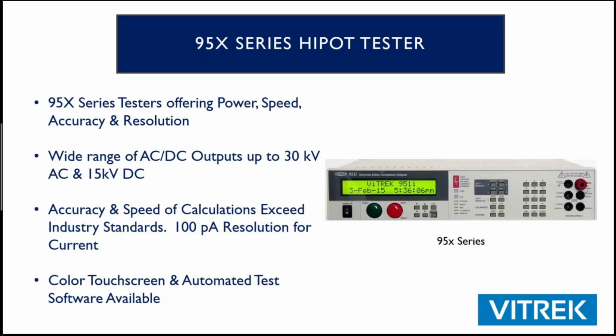So our other product family is the 95X. This product is more powerful, more accurate, and has a wider output voltage range. We can go to 15 kV DC, 30 kV AC. It's the most accurate tester, or as far as a HIPOT tester, that I'm aware of anyway, with 100 picoamp resolution. A lot of people will say, why would I need 100 picoamp resolution when my standard calls out for 5 milliamps? That seems like total overkill.